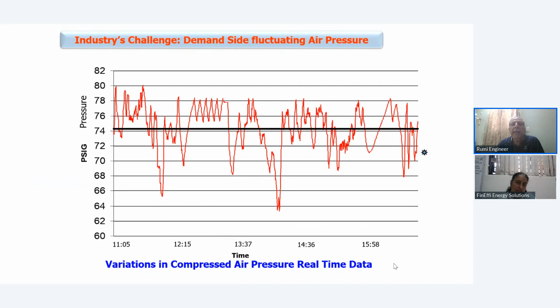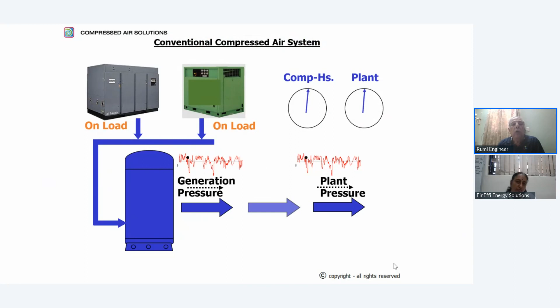To overcome this, what people do is overpressure - they set more pressure to compensate, and then supply the air. This is how you see it in a conventional setup. You put more pressure so there's no pressure drop in the plant. But there is a solution to that.